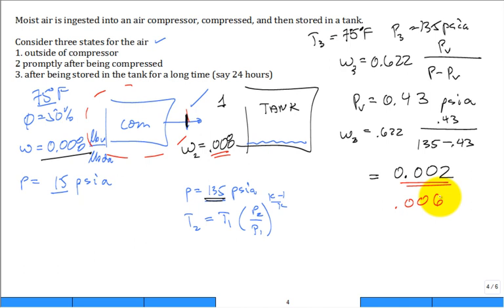That's a lot of water. Now, we picked conditions that aren't that dramatic. If you're in Houston at 95°F and 60–70% humidity, you're going to get a lot more water in your tank. If you're in El Paso, not so much. It depends on how much humidity is in the air you're ingesting into the system.